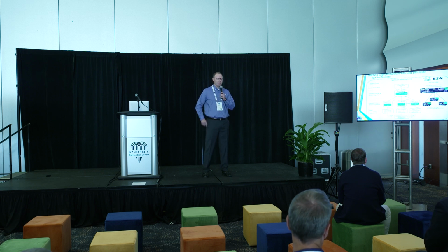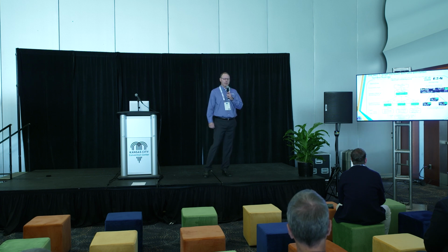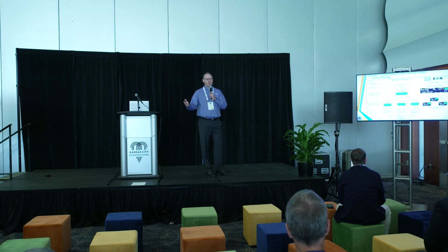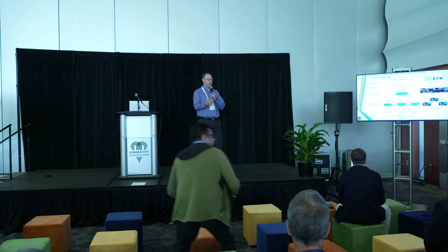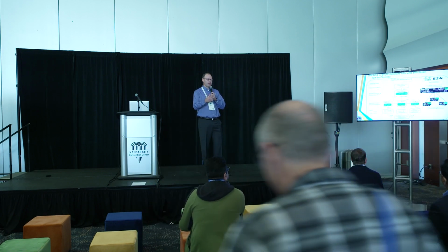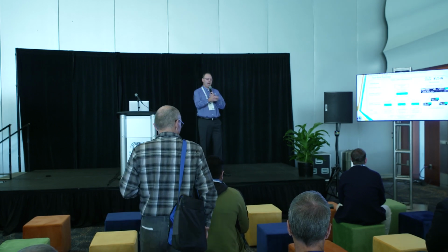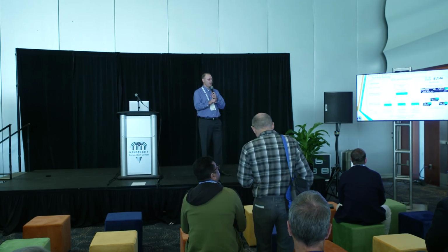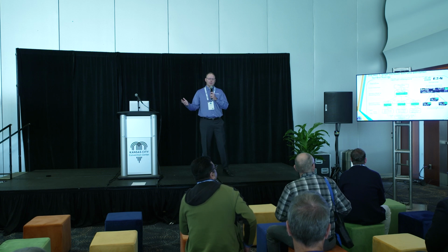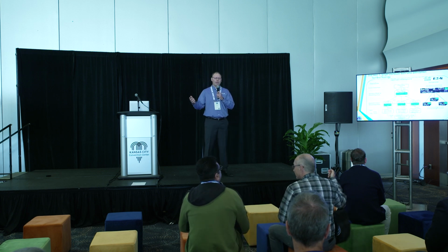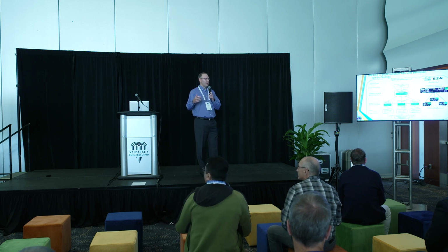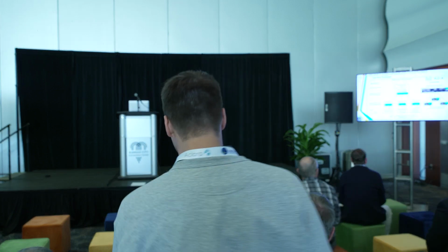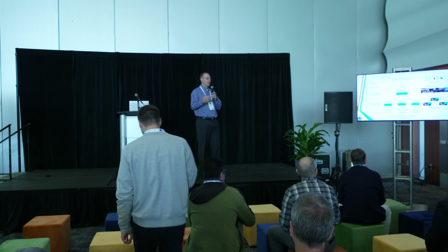But with this demonstration, we can use a digital twin of the grid. We're using a real-time grid simulator to emulate how the actual physics of the grid would behave, and then incorporate that distributed energy resource system in a way that not only can tie in safely and reliably, but can be optimized in a peer-to-peer fashion with the voltage regulators. As Dan mentioned, you can optimize them in a way that can even extend the life of your capacitor bank and voltage regulator, which, if optimized, do not operate as frequently when you have a very volatile, variable grid.